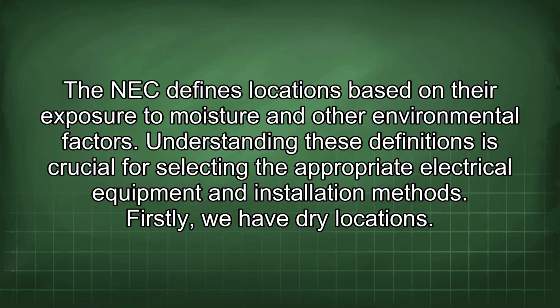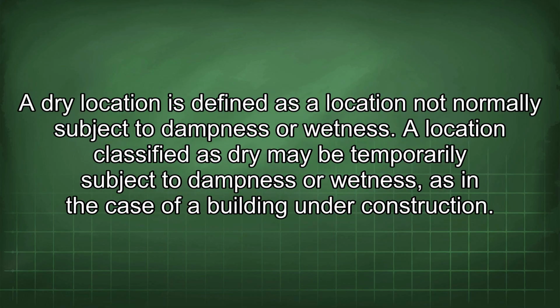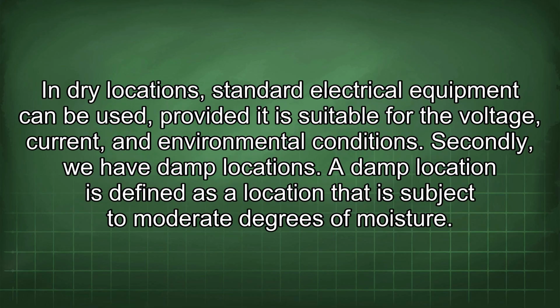Firstly, we have dry locations. A dry location is defined as a location not normally subject to dampness or wetness. A location classified as dry may be temporarily subject to dampness or wetness, as in the case of a building under construction. In dry locations, standard electrical equipment can be used, provided it is suitable for the voltage, current, and environmental conditions. Secondly, we have damp locations.